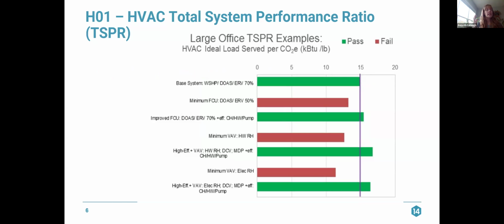I did pull a really nice study that was done by DOE on the types of systems that can comply with the TSPR method. And this is the example for large offices. Your base system for a large office is a water source heat pump with DOAS and ERV, and then it goes through the comparison of all of the different system types and if they would comply with the TSPR method. So it does require additional efficiency over just the prescriptive requirements. Just looking through this, if you have a rooftop unit with hot water reheat, you're not going to comply with the TSPR method.